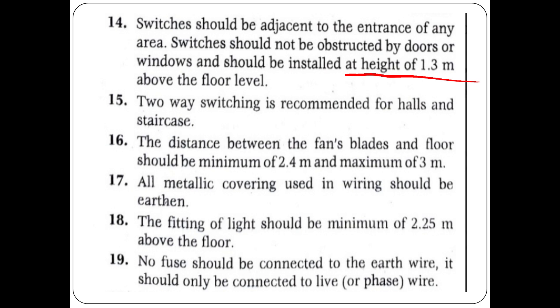All metallic covering used in wiring should be earthed. The fitting of a light should be a minimum of 2.25 meters above the floor.